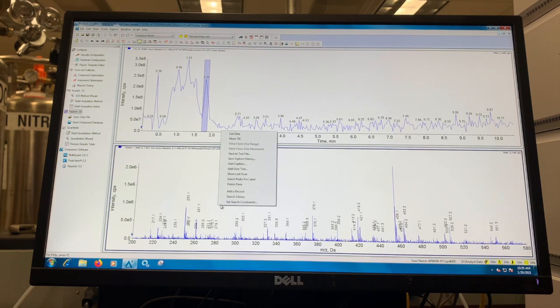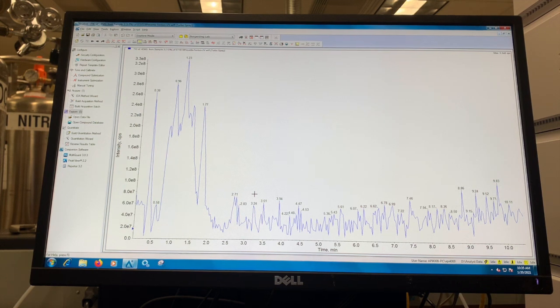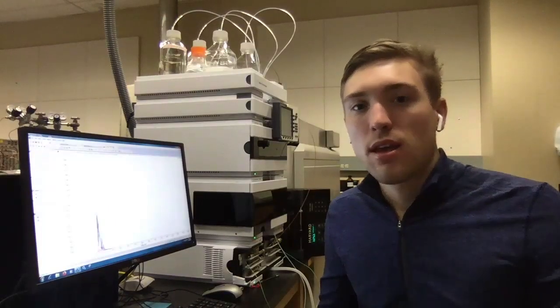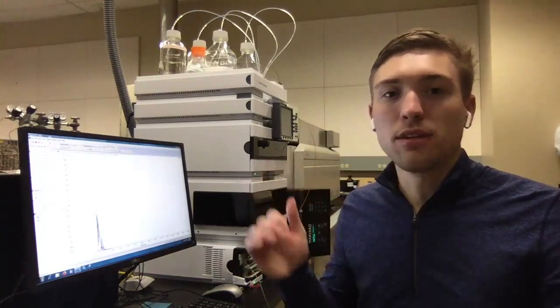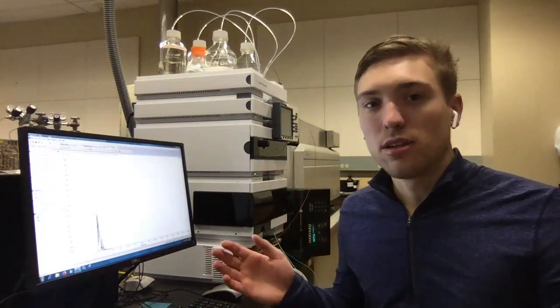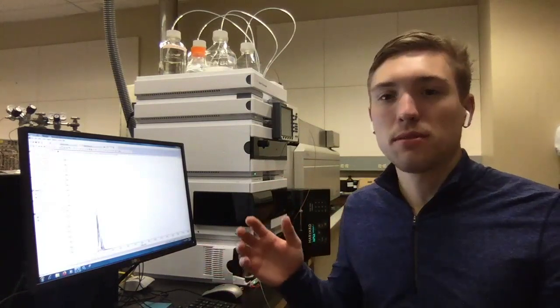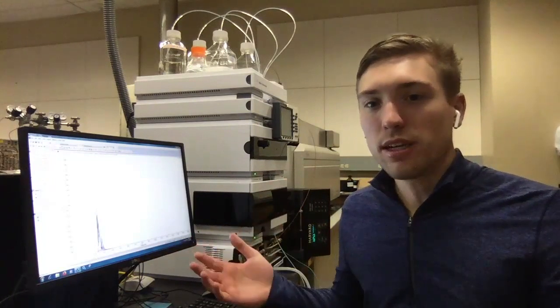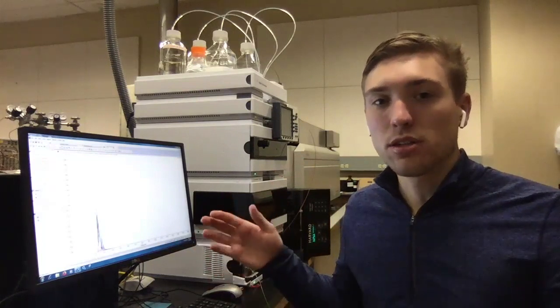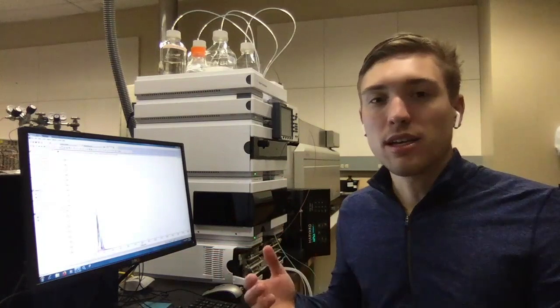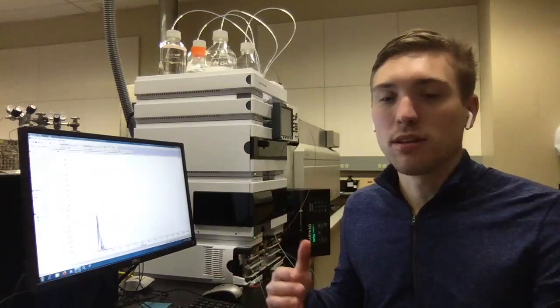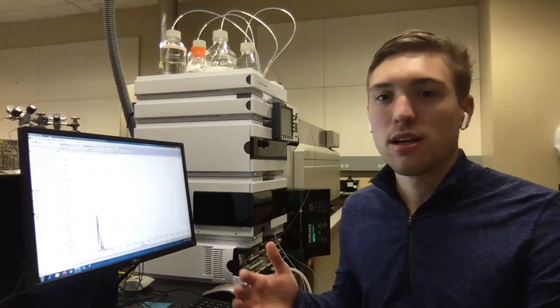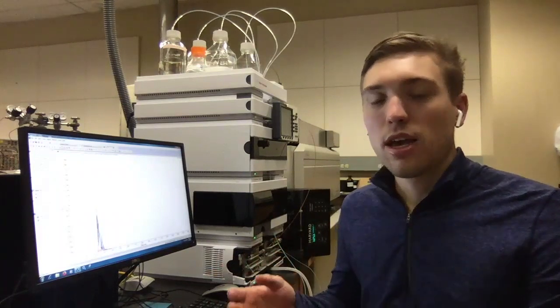So these are the main benefits of the EMS method in that you have an ability to detect a wide range of masses and then you can actually extract each mass into its own chromatogram later. The next method is selected ion mode or SIM. And this uses just one of the quadrupoles to select a certain list of M over Z values that you can input into your method and send these to the detector to be shown in your output. And this method of detection will show an overlaid chromatogram with several different colors, each color representing one of your analytes that you put in. SIM mode has the added benefit of better sensitivity. However, it's more selective, so you may miss some of the potential analytes that are in your matrix. So this method I use when I already have a good feel of what my M over Z values are going to be and if I need any added sensitivity in my method.